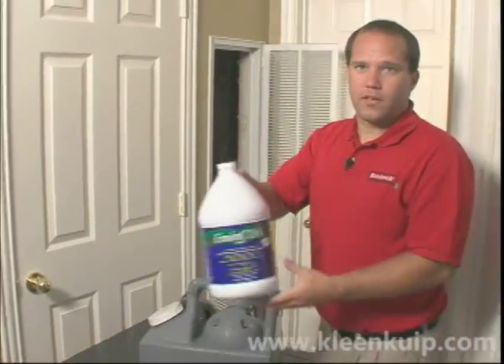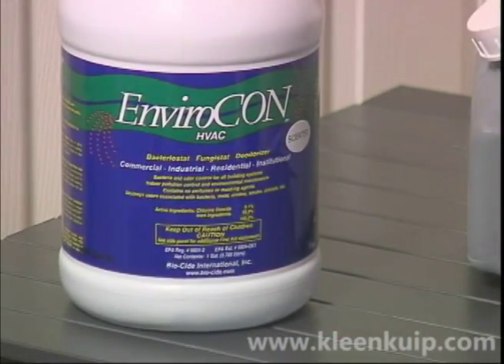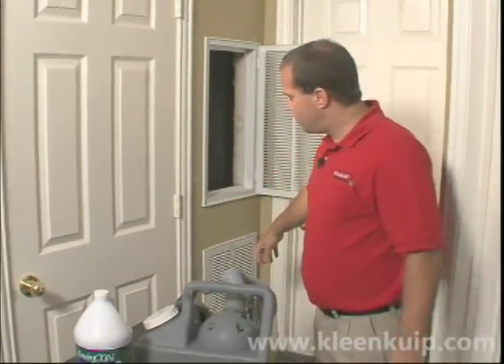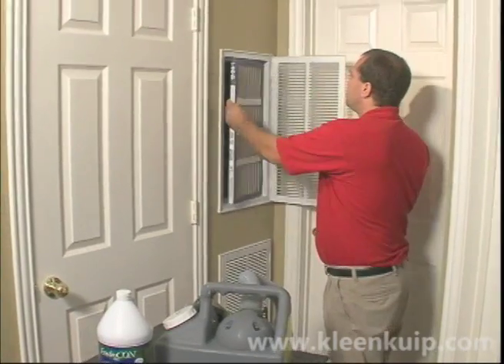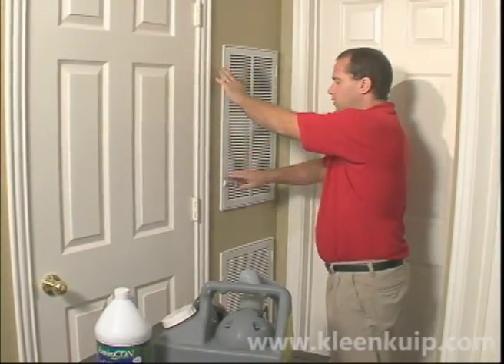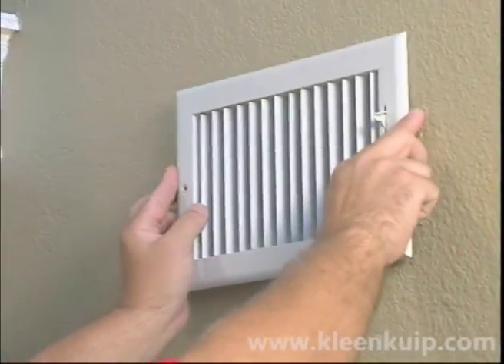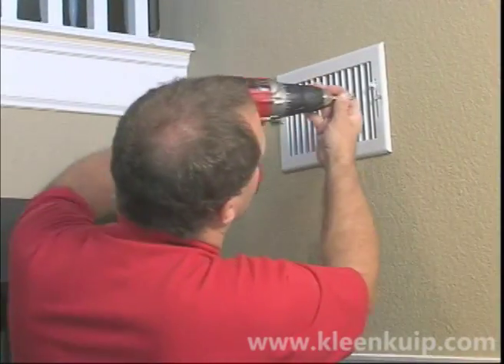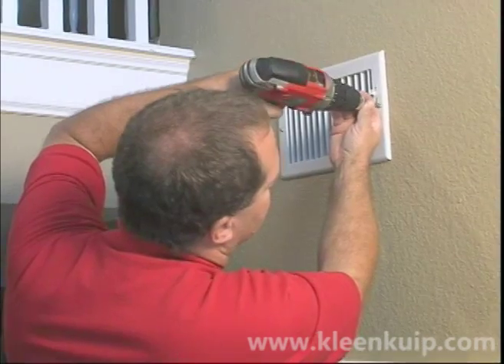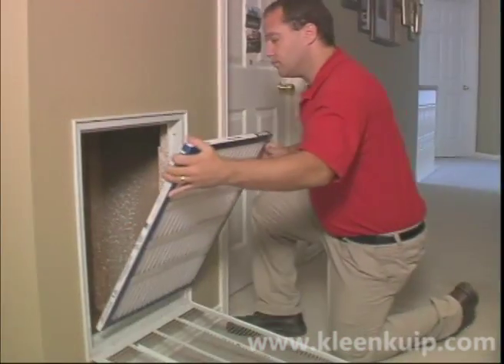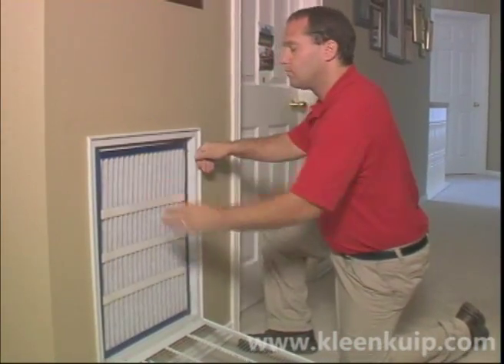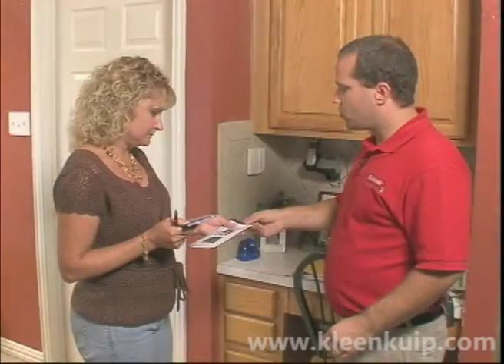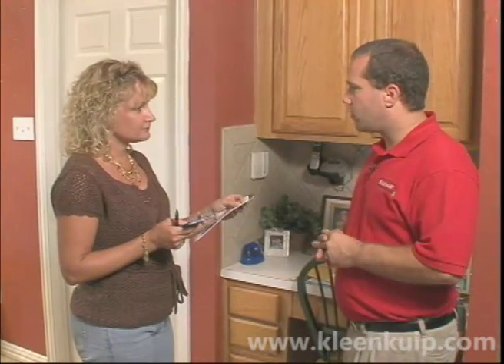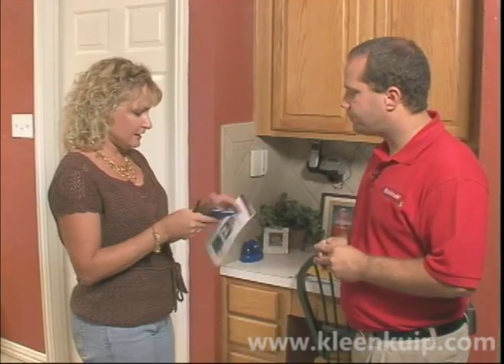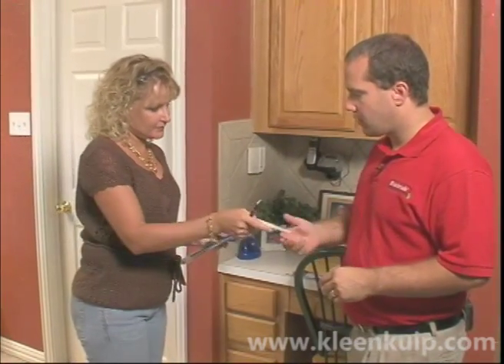Also, keep your chemicals in a climate-controlled environment to prolong their life. The last thing we need to do is install the filter, close the door, and turn on the air handler. When the cleaning's done, replace the registers, making sure that the direction of the louvers moves the air in the desired direction. Replace the filters and collect payment from the customer. Use this time as an opportunity to ask for referrals, as well as describe any other services you may provide.